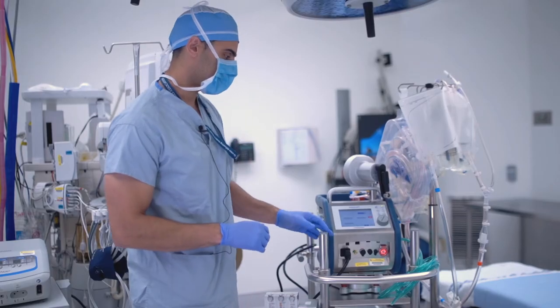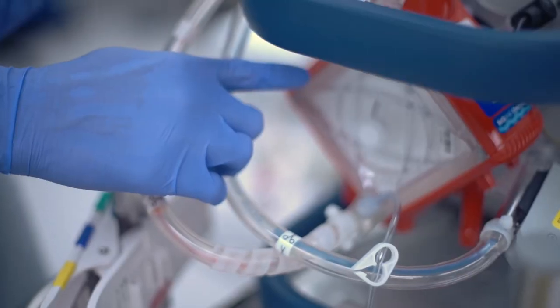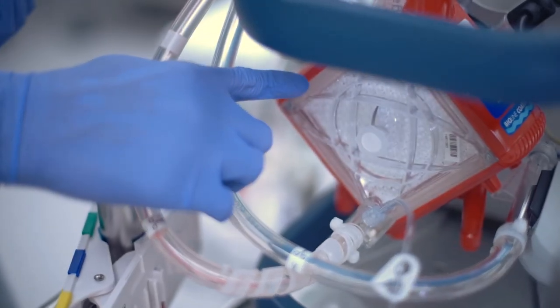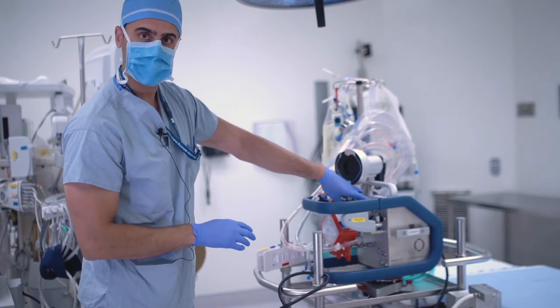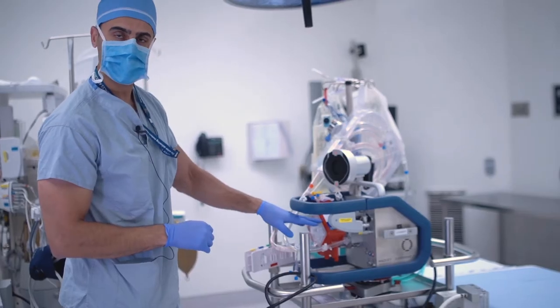When we use this machine, the console is the CARDIOHELP here, and on the back this is the oxygenator. Behind it would be the actual pump. The oxygenator would act as the lungs for the patient, and the pump behind it would act as the patient's heart in case their heart was failing.